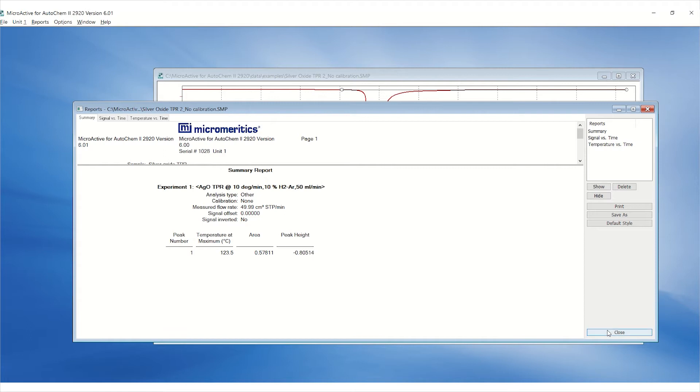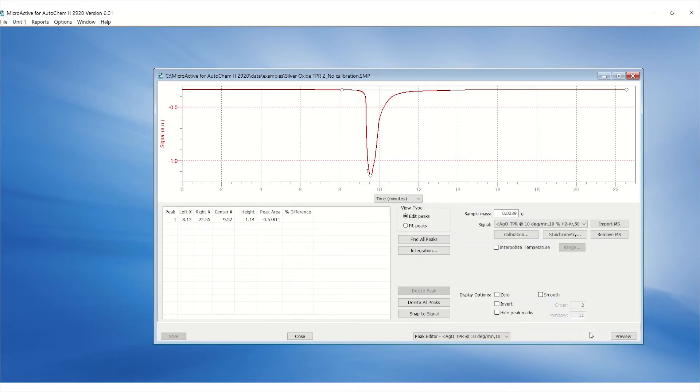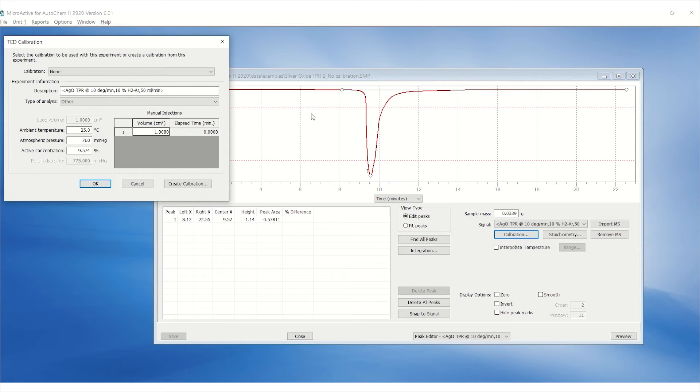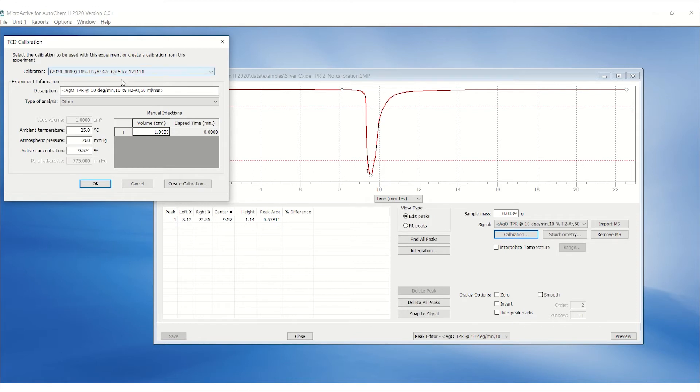The calibration may be updated using the peak editor. Simply click on calibration and select the appropriate calibration file. The calibration should have the same flow rate and be from the same gas cylinder used for this experiment.